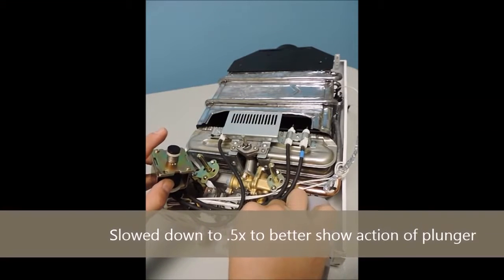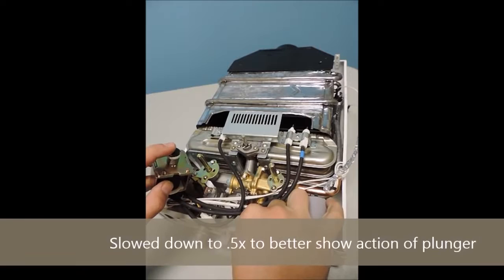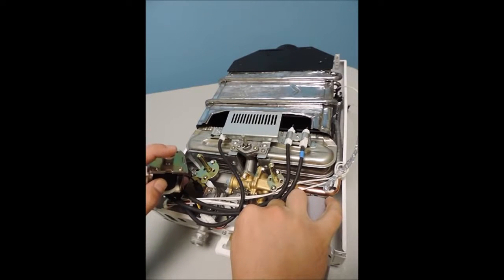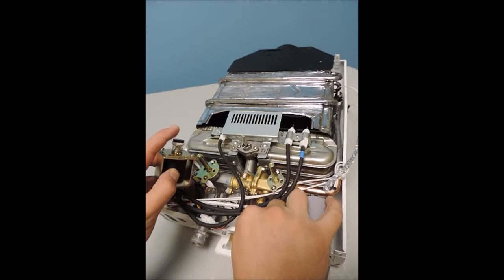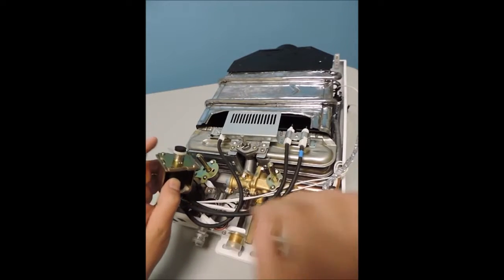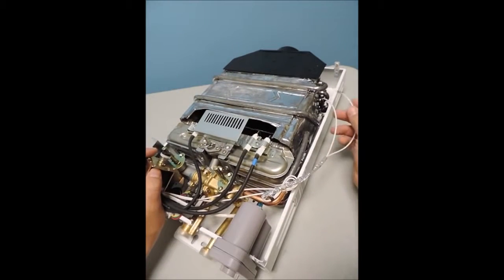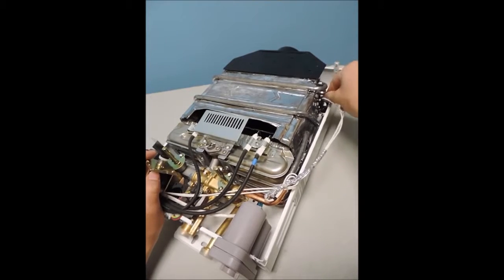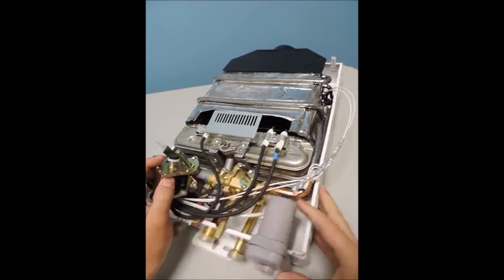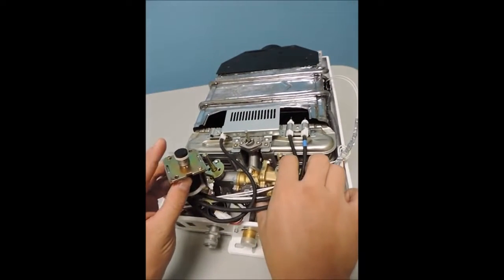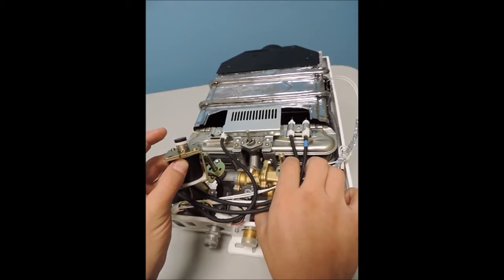Here is an example of a malfunctioning gas solenoid. The solenoid plunger should stay in the open position for roughly 15 seconds. As you can see here, it is immediately resetting to the closed position. If this is the case, then confirm all electrical connections are firmly connected, especially the black clip connecting the solenoid and also the connections on the overheat protection sensor.